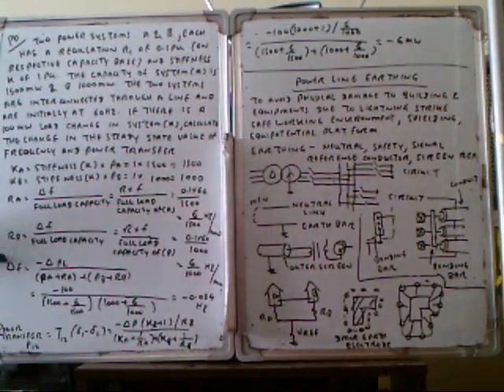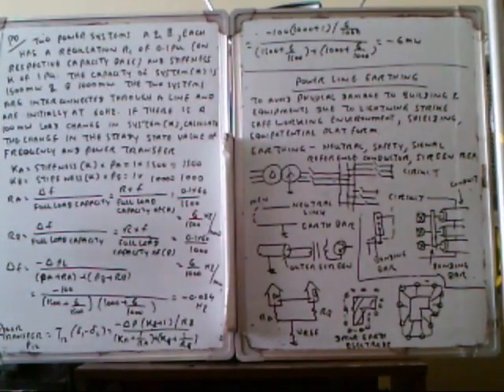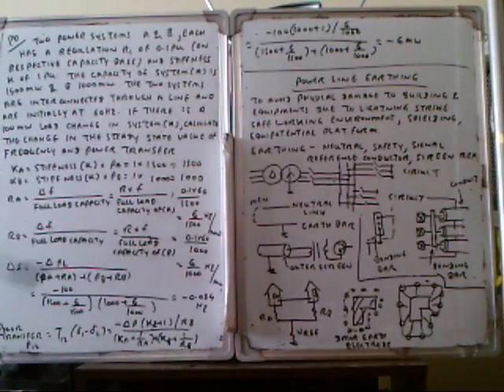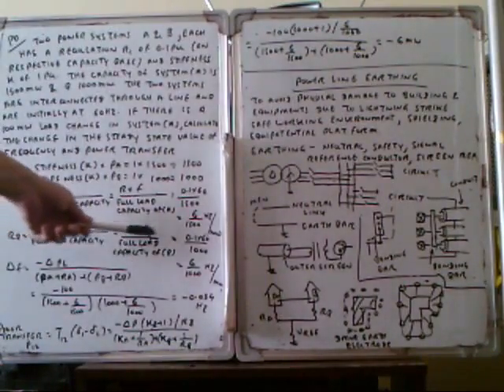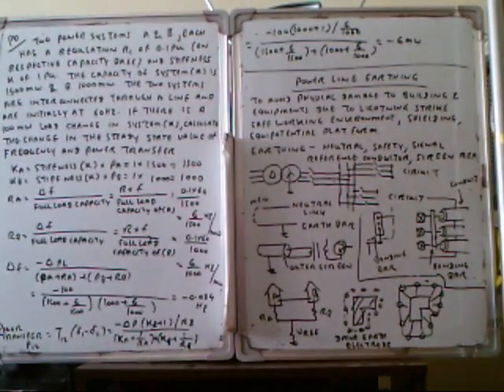R_B is the regulation for system B. R multiplied by F divided by full load capacity of B. R is 0.05 per unit, frequency is 60, and full load capacity of B is 1000, so this becomes 6 divided by 1000.